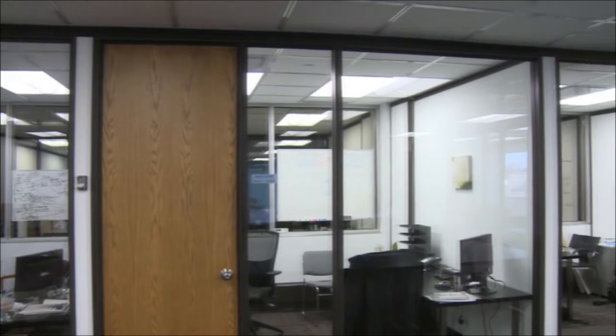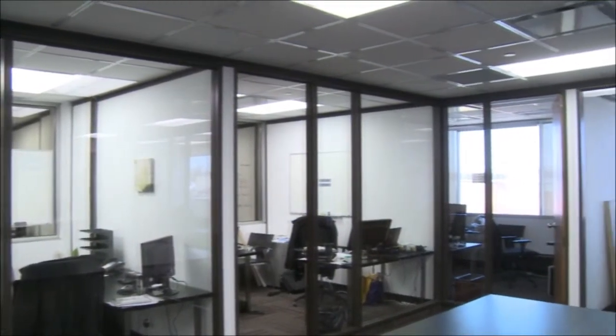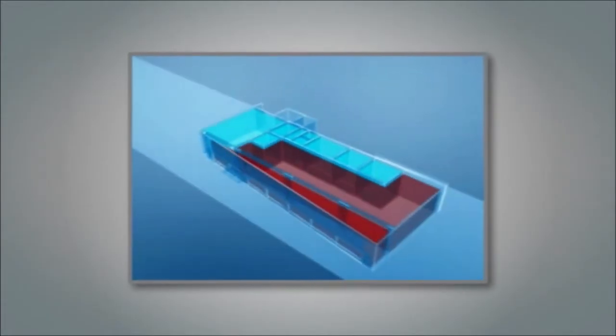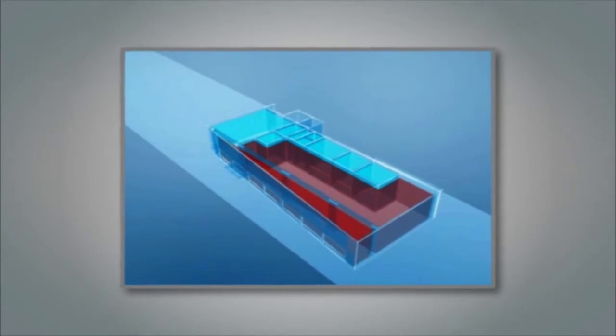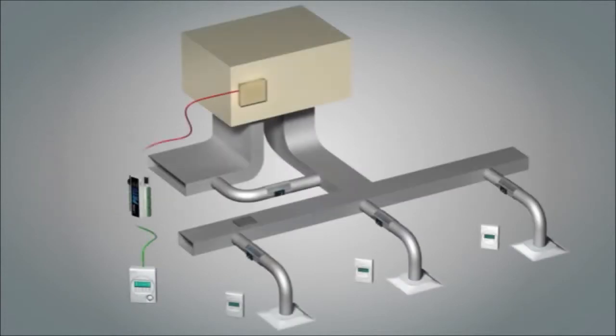In the past, packaged rooftop units, split systems, heat pumps, and air handlers were controlled from a single standalone thermostat. This thermostat alone would determine the unit's operating mode, even if conflicted with the demands of the individual zones fed by the system. Today, with modern open communication protocols such as BACnet, it is possible to directly gather real-time load information from each individual zone fed by the rooftop unit. This ensures the system is operating in the mode which best serves the needs of all the occupants, which maximizes comfort, saves energy, and cuts operating expenses.